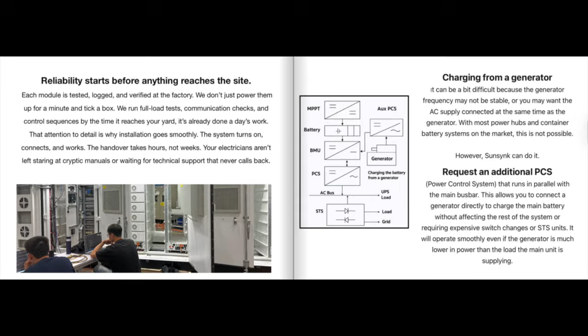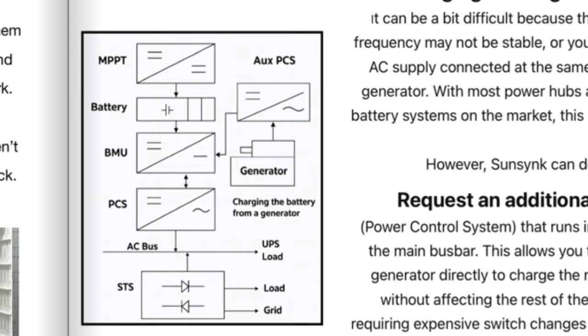What's the benefit? Well, the benefit is, one, the generator doesn't have to hold the full load if it's ups and downs, because the inverter can be just discharging the whole time. It's not going into charge mode. It's only in discharge mode. The generator is directly inputting onto the DC side of the power hub, on the battery. So it's directly into the DC side. That means if the frequency is up and down, it doesn't matter, because that PCS will lock into that generator, because it has to lock. And the generator, you choose how much power you want it to run, and whatever capability the generator has, you match that secondary PCS to it, and that will directly charge the battery. Because as I mentioned before, the frequencies have to match.